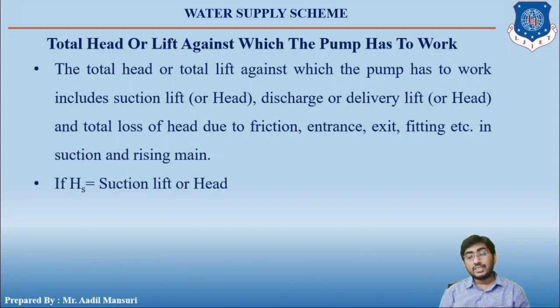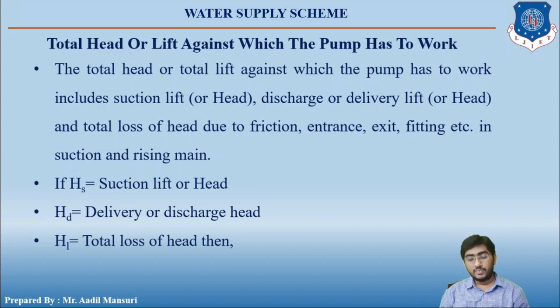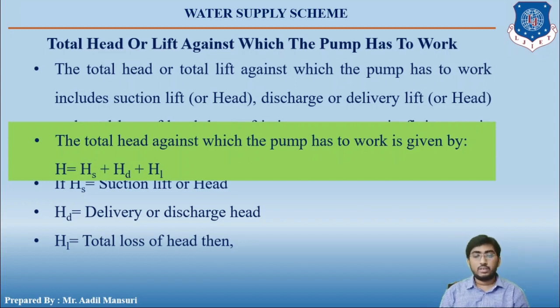If hs is the suction head, hd is the delivery head, and hl is the total loss of head due to friction, entrance, exit, etc., then the total head against which the pump has to work is given by: H = hs + hd + hl.